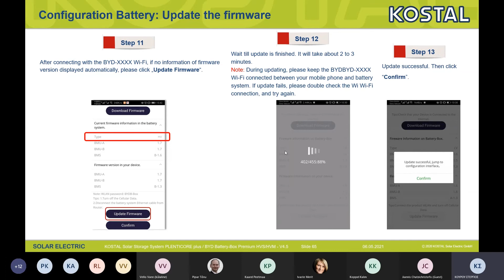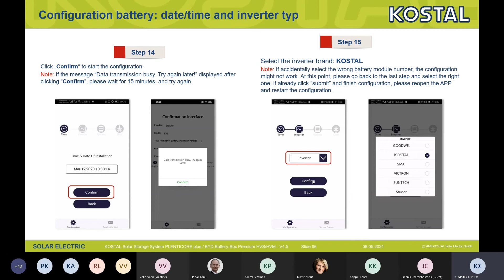Just set the time and confirm. Then pick the Kostal inverter from the inverters list and confirm. There are two more steps to finish configuring: first the system, choose the battery type, HVS or HVM, and confirm. Then select how many modules you have installed, 1 through 7, and confirm again.